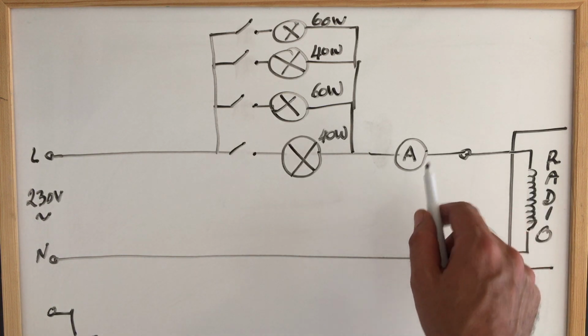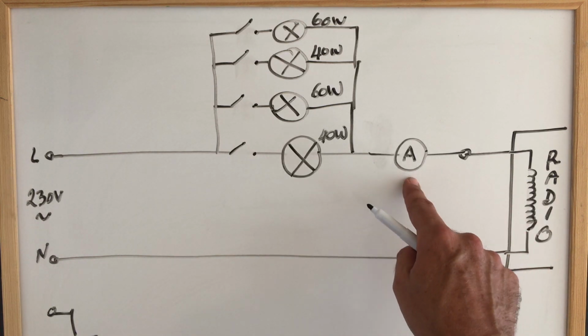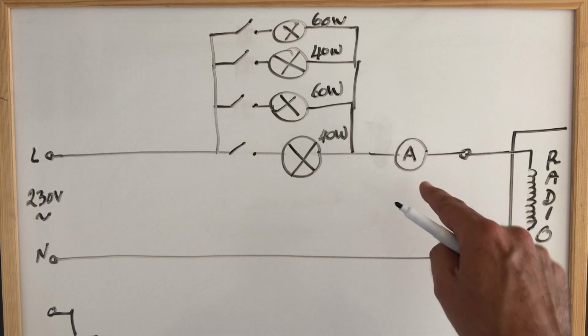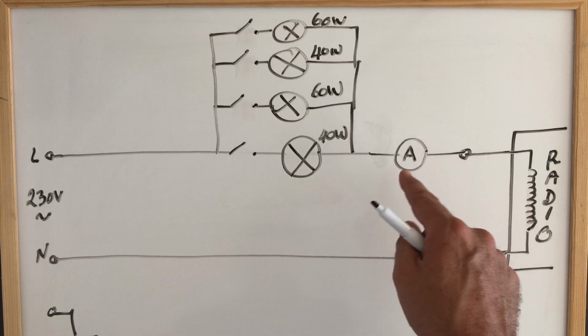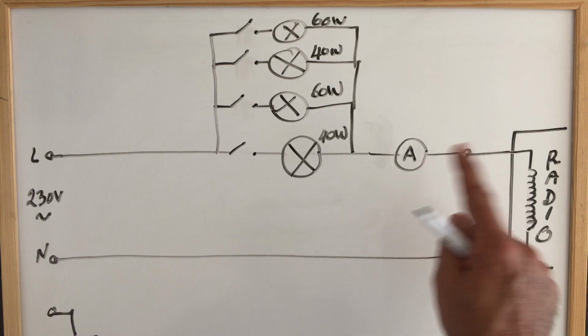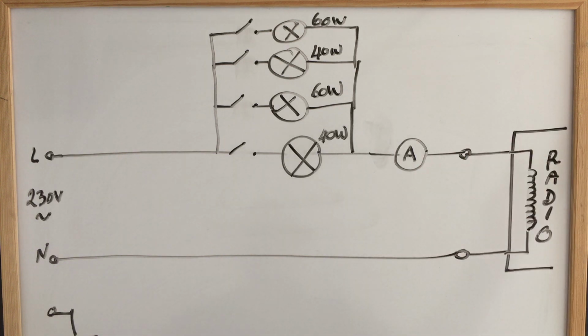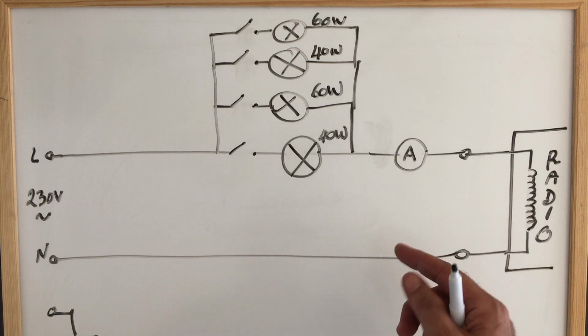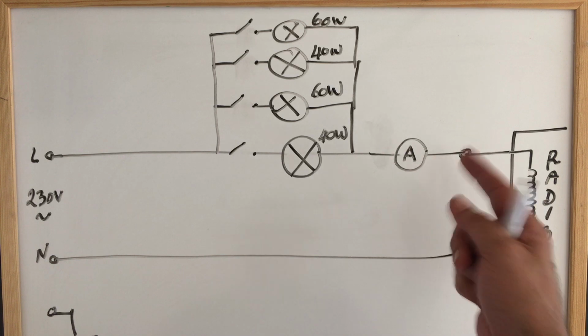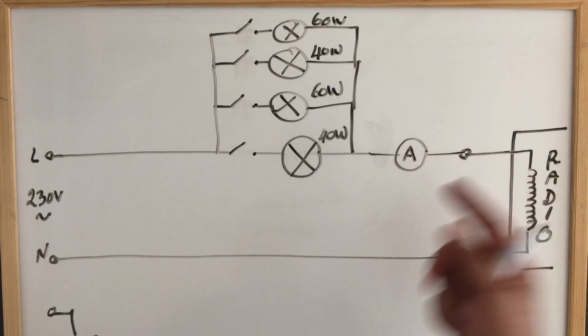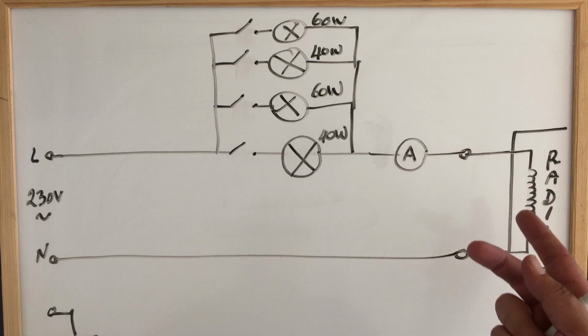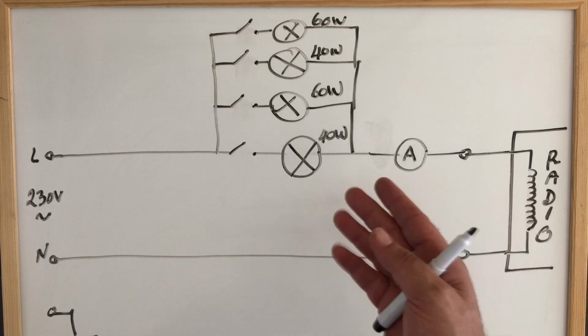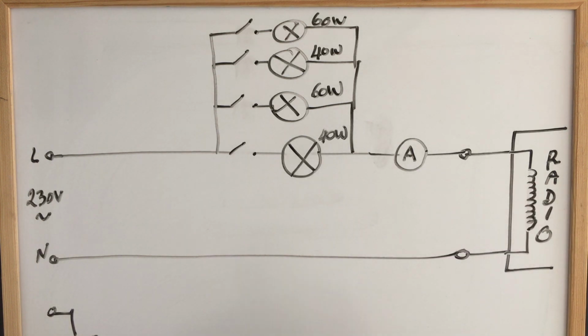The one peculiarity about this, the way I've wired it, is it comes with a sort of toroid, and to measure current you put the wire carrying the current through the toroid, which gives you 0 to about 10 amps or more. I wanted to read smaller currents, so I made the wire go through 10 times, which means say 100 milliamps will read as 1 amp. So I'm basically just changing the decimal point on the meter, and I marked that on the face itself, as you probably see.